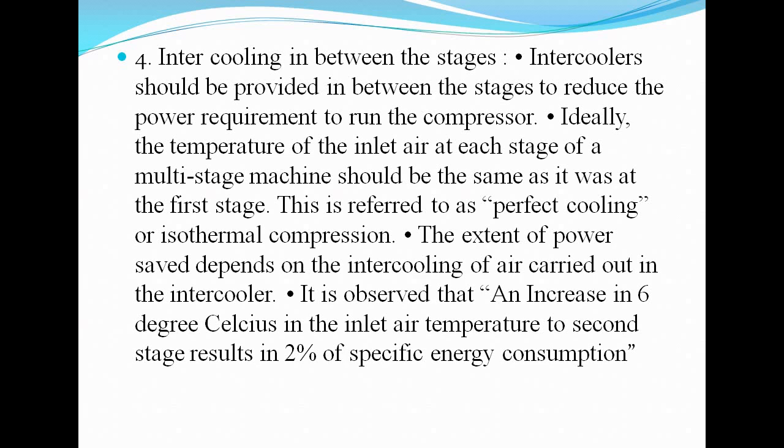That means, suppose there are three compressors connected, that is a multi-stage machine, then the inlet temperature of the first stage should be equal to the second inlet and third inlet. This is referred to as perfect cooling or isothermal compression. The extent of power saved depends upon the intercooling of air carried out in an intercooler.